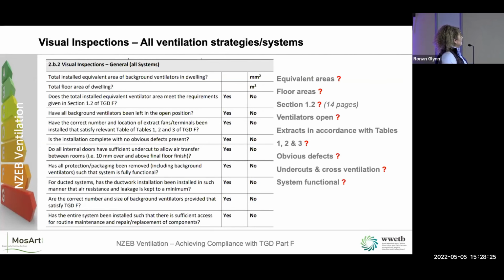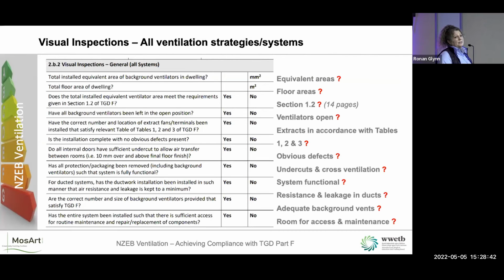Is the ductwork insulation good? Is there any air resistance or leakage? When we're talking about air resistance, we're talking about shoddy ductwork with too many bends on it, not going from A to B in the shortest run possible. Do we have adequate background ventilators? And is there room for access and maintenance? That's something we really do have to start looking at. That's for all ventilation strategies.